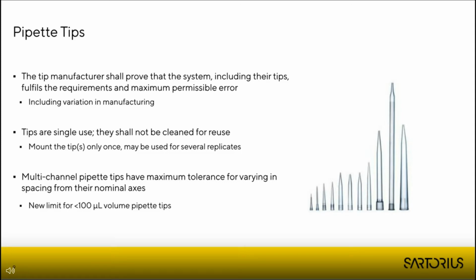Then what else changed when it comes to tips? It's much clearer now that tips are single use, meaning you can mount the tips once, but obviously you can use the mounted tip for several replicates. So you can use the tip multiple times when it's in a pipette, but when you mount it and eject it, then it's done. The tips shall not be cleaned for reuse.